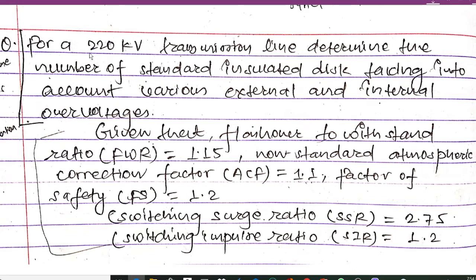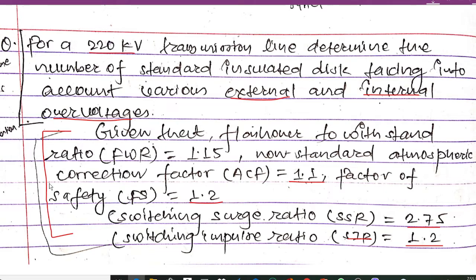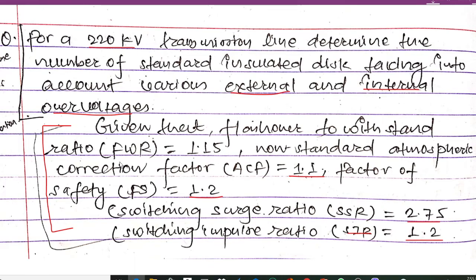We have a 220 kilovolt transmission line and we have to determine the number of standard insulator discs, taking into account various external and internal overvoltages. Given data: flashover withstand ratio FWR = 1.15, atmospheric correction factor ACF = 1.1, factor of safety FS = 1.2, switching surge ratio SSR = 2.75, and switching impulse ratio SIR = 1.2. Sometimes these values are not given in questions, so we must remember them.